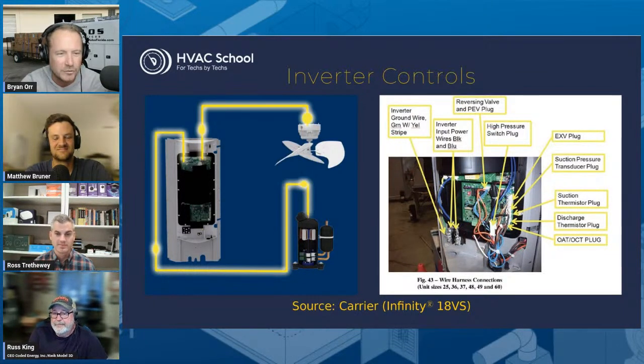And you can do that because now we have technologies like vapor injection, so we can keep the compressor cool enough, or interstage cooling, whatever the case may be. There's a lot of different terms that people use for this in different parts of the industry. We use it in market refrigeration. We've had interstage cooled compressors for a long time in R22, where you're trying to do a lot more with a single refrigerant than you normally would be able to. And it really comes down to inverter technology and compressor technology.